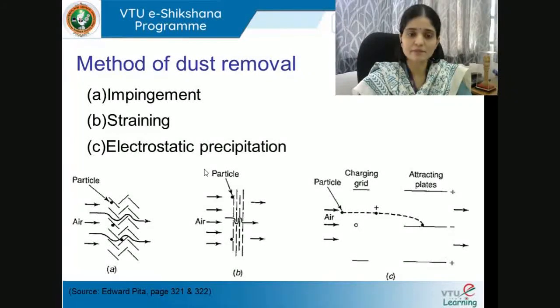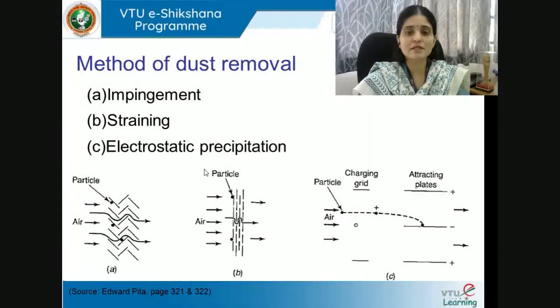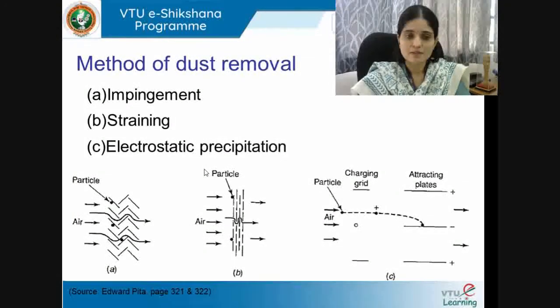To summarize: impingement means the impurity gets stuck to the filtering media; straining means the impurity remains on the outside of the filtering media and does not enter the AC system as air moves through to the evaporator; electrostatic precipitation uses charged air particles and electrostatic fields to arrest impurities.